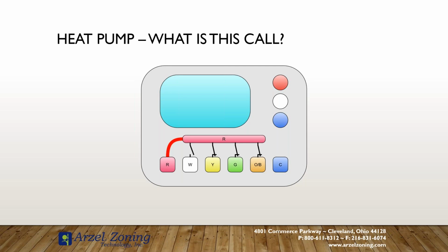So if you have the Air Boss or the MPS panel, the O terminal and the B terminal on your HVAC outputs are separated. If you have the MPS or the Air Boss and a piece of equipment that energizes in heating, such as the Rheem Ruud, then your reversing valve wire from that equipment hooks up at the B terminal, B as in boy. However, the thermostat still has to energize that reversing valve on a call for cooling. So when I look at this thermostat call and I think about the RZL panel, the O/B terminal is closed, that has to be a call for cooling from the thermostat, because the RZL panel is what controls your reversing valve. So then when I look at the reverse of that, my reversing valve terminal is open now. I know that's a call for heat.